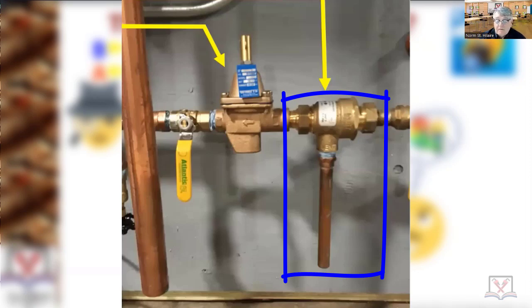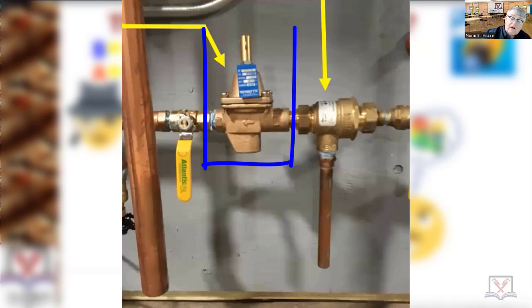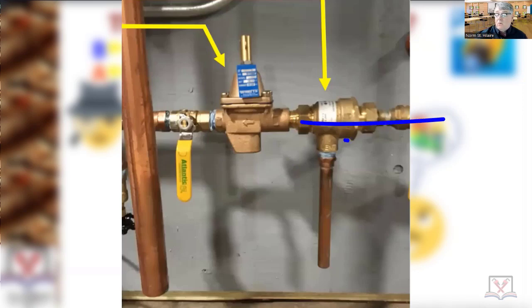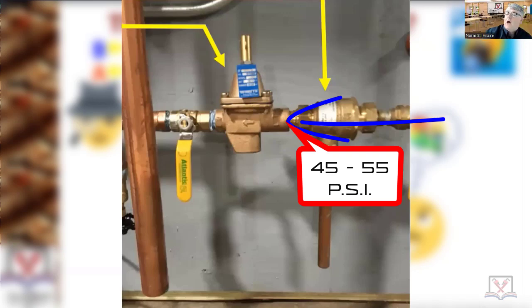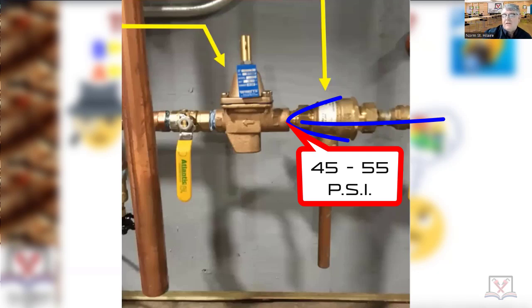If it has an automatic fill, maybe part B goes on a steam boiler, but other than that this device is not used there. What is the A device doing? If I have water service coming through, bringing my water pressure in — most of the time we're going to be anywhere between 45 to 55 PSI coming to this point. What is this actually doing? It reduces the pressure for the boiler. The set pressure on that device should really truly never go over what?